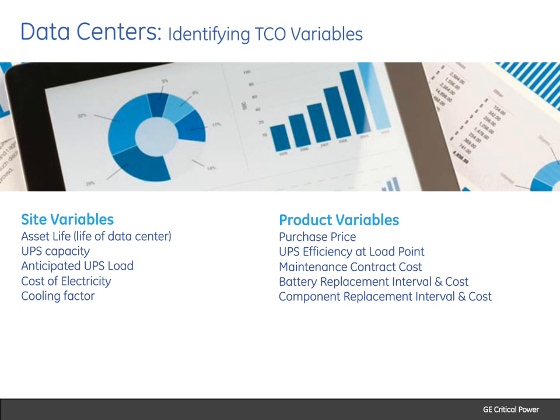The other variable is the UPS and its load. The analogy here, to Harry's point, is if you look at a 10-megawatt data center where the load is very, very high, the impact is very great. If the load is much lower, say partly loaded at very low loads, then efficiency won't matter nearly as much.